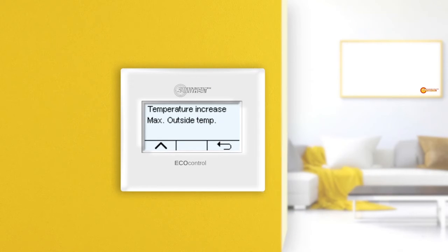What is the Maximum Outside Temperature menu? In the menu Maximum Outside Temperature, the outside temperature up to which the Sunny Heat infrared heating should carry out the switch-off bypass is specified. The maximum outside temperature can be set up with the plus button or down with the minus button. We have entered an outside temperature of 12.5 degrees Celsius. If the outside temperature is higher than 12.5 degrees Celsius, the switch-off bypass is not active. If the outside temperature is 12.5 degrees Celsius or lower, the switch-off bypass becomes active in the time periods.